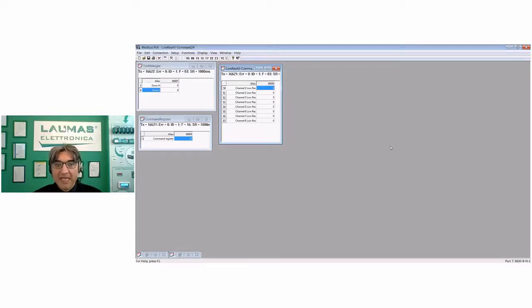So on TLM8 you can see only one calibrated weight value on the display, but if you use a Modbus or another field bus, you can read the raw count coming from the ADC for every single channel. They are basically the millivolt values converted into digital. So they are 24 bit values, unfiltered, not equalized, and not calibrated. So really raw values.